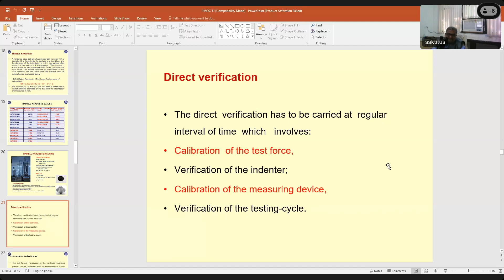For testing of the forces, we can use even the class 1 instrument, which is calibrated as per ISO or IS 4169 standard. So 0.05 class or class 00, not class 1. These are the load cells you can use for calibrating the forces, because the force requirement is F plus minus 0.1%.